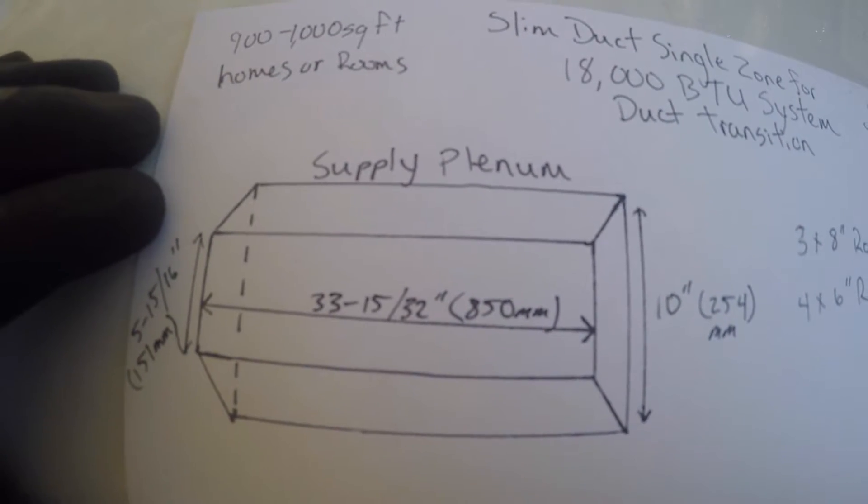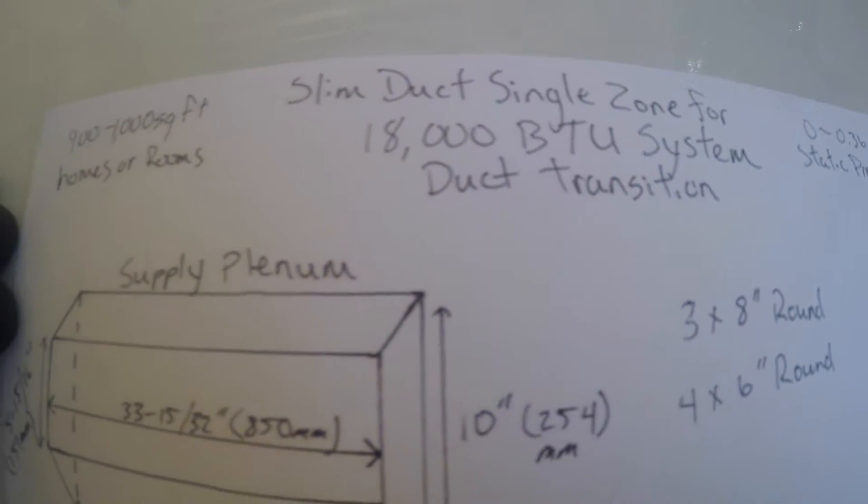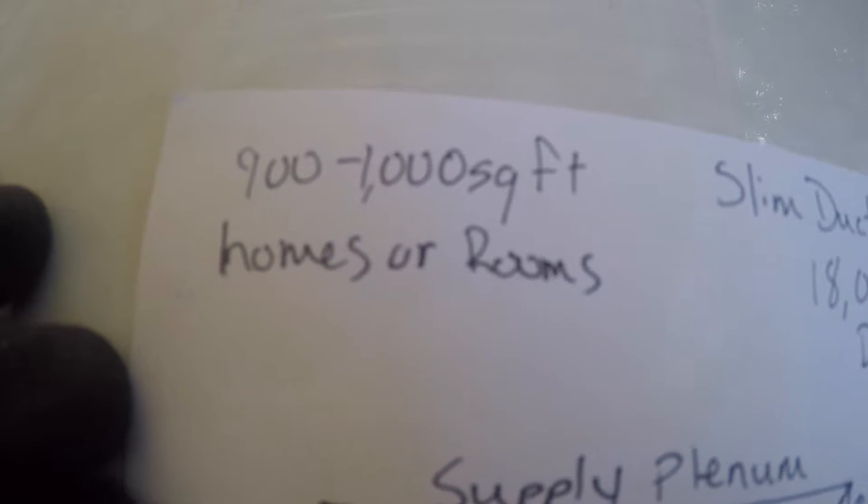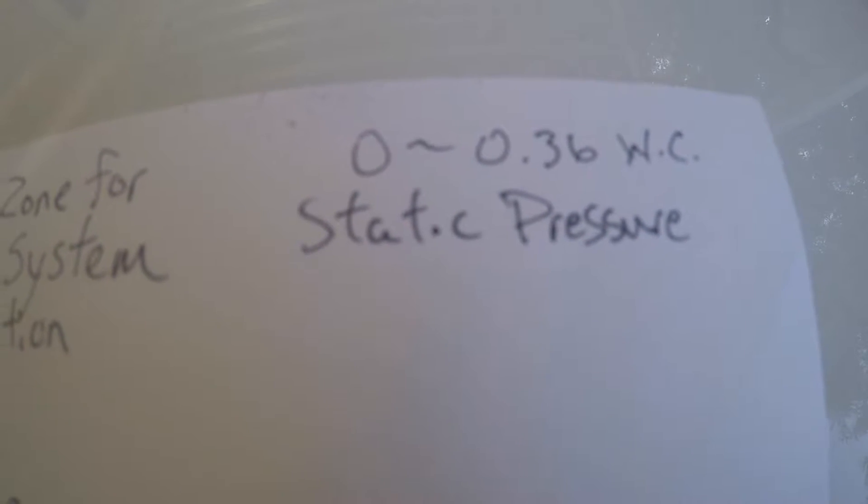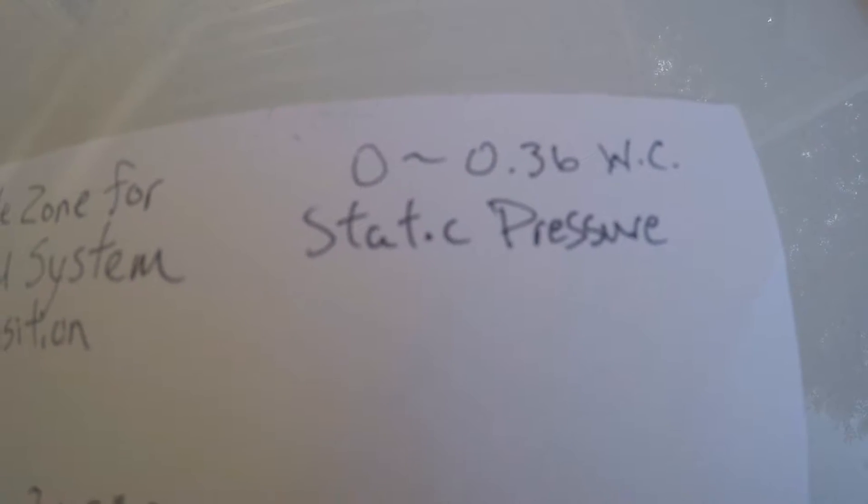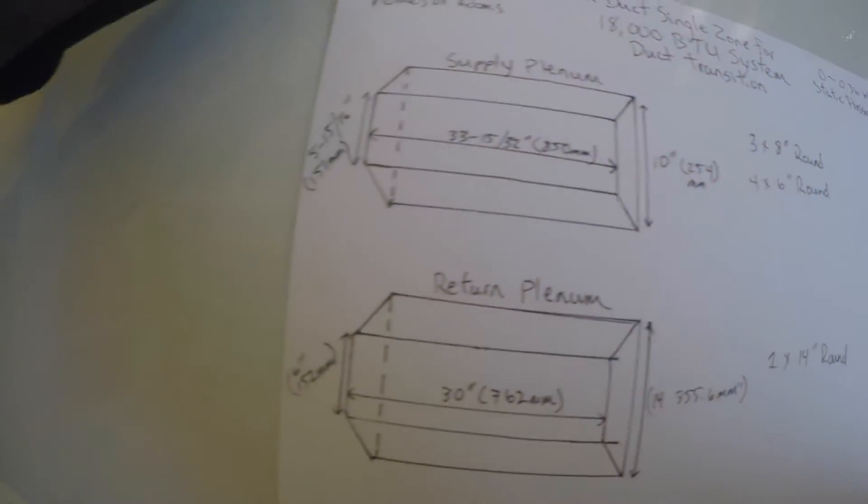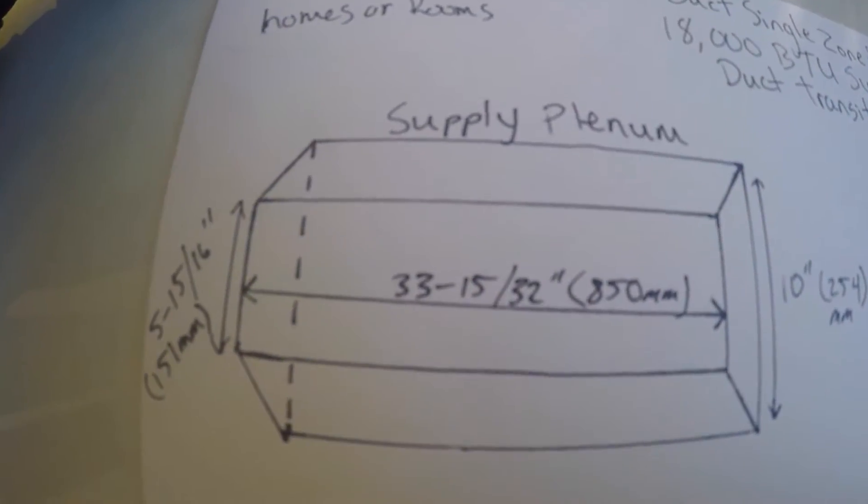So you pretty much have to build them yourself. This is rated for a 900 to 1000 square foot home or room or area, and our static pressure that we need based on manufacturer is 0.36 inches of water column.